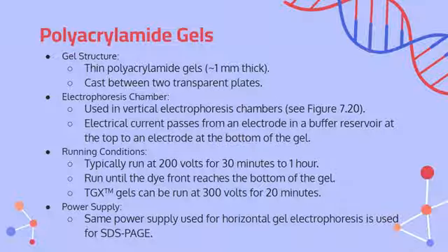It typically runs at 200 volts for 30 minutes to an hour, and it runs until the dye front reaches the bottom of the gel. We can see TGX gels be run at 300 volts for 20 minutes for faster results. The same power supplies used for horizontal gel electrophoresis can be used in SDS-PAGE.